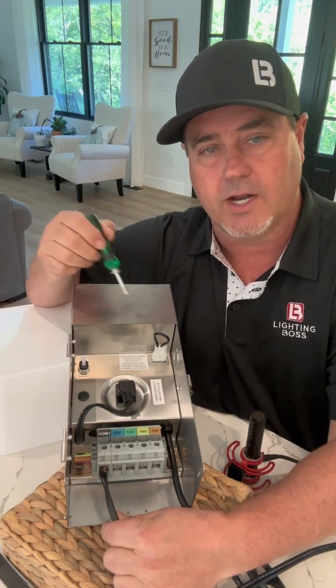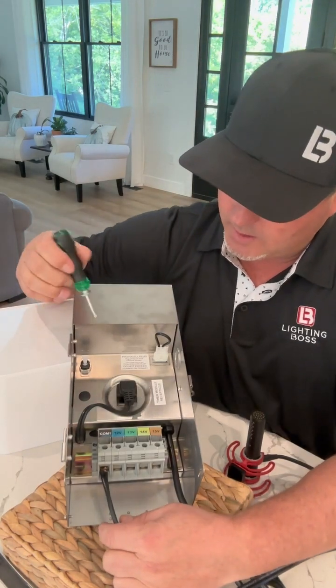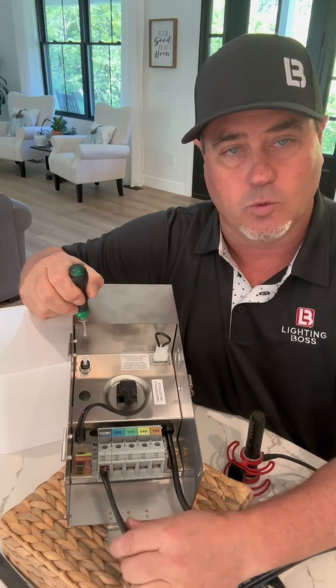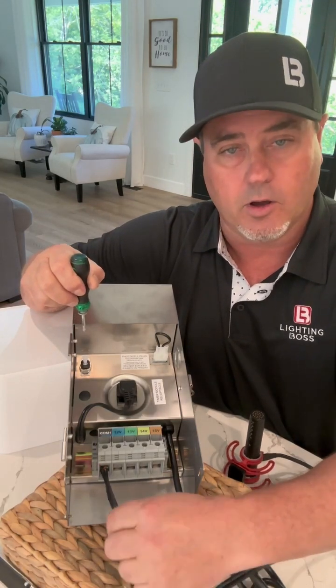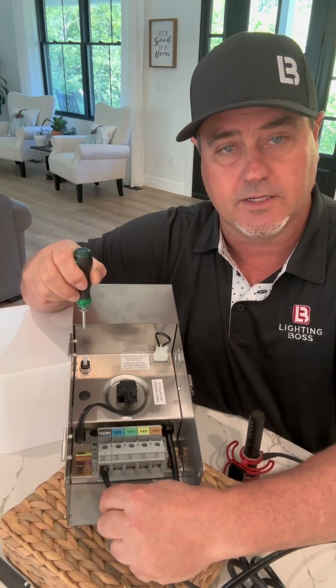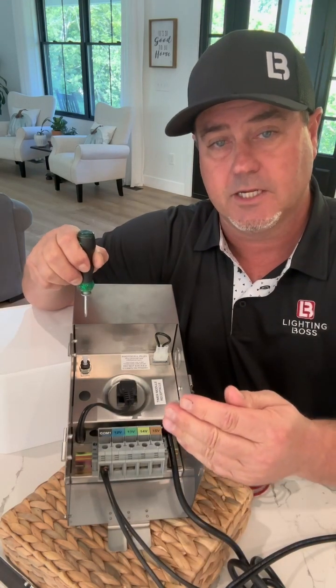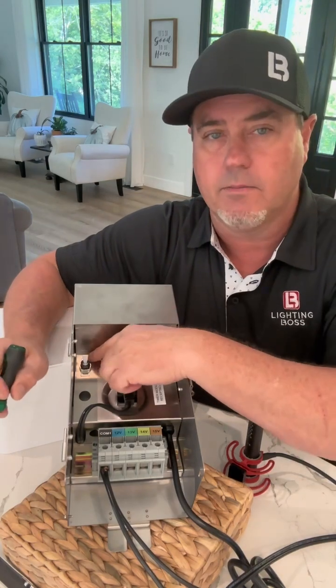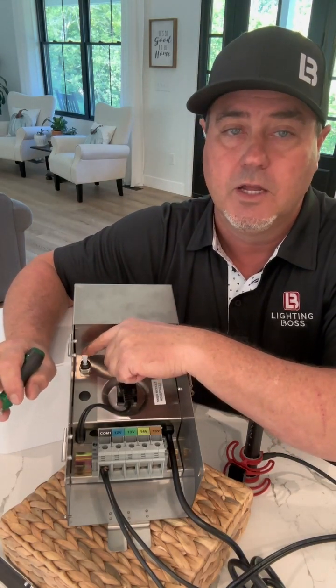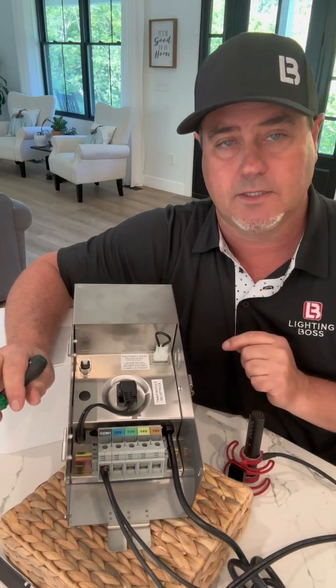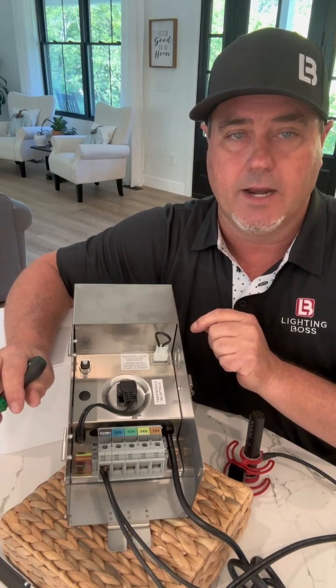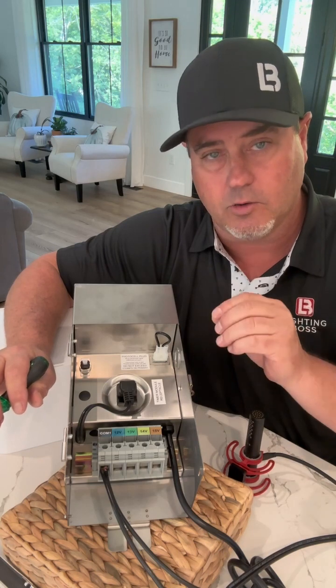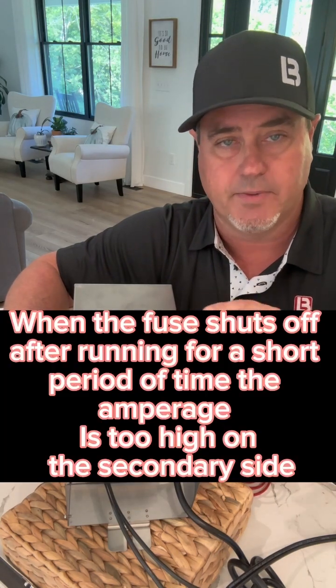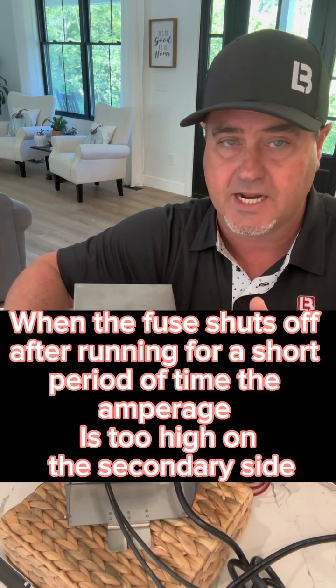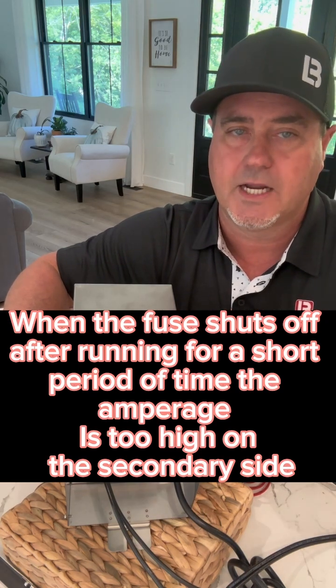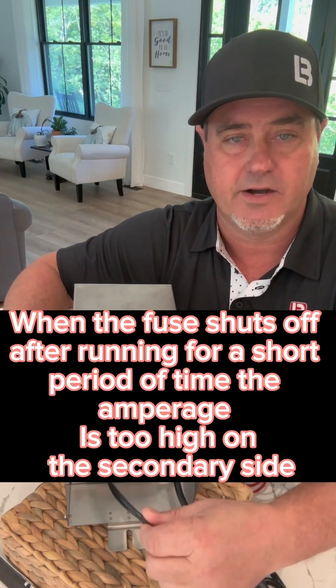And this is a 300 watt transformer, just so you know. So if I were to exceed 25 total amps going in on all my lines, when I test all my lines into the transformer, it might not happen immediately, but within a minute or so it's going to trip this secondary fuse. And it's a very good sign when it's a slow blow, is what I call that. When it takes a minute, operating for about 30 to 40 seconds and then turning off, that's a real good sign that you've got too much amperage on your secondary side.